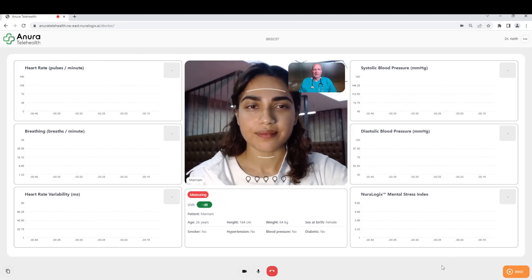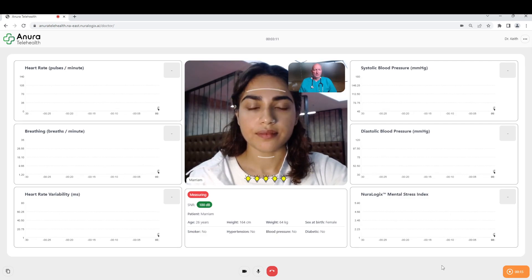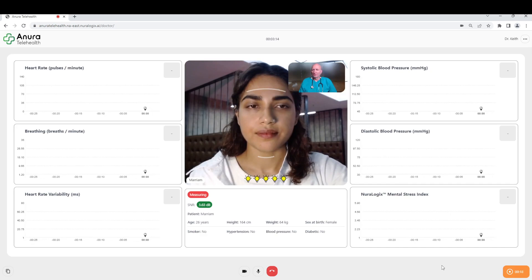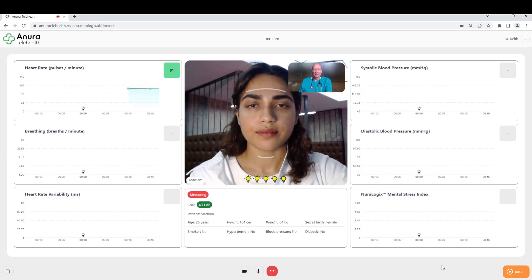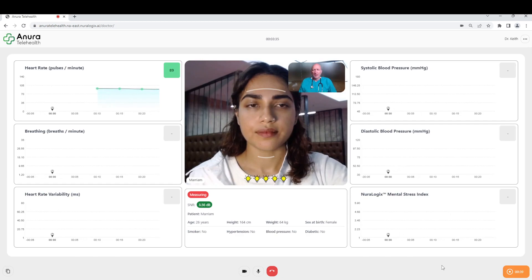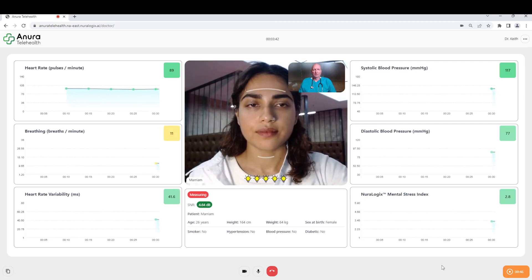If I were visiting you by telemedicine conference, Miriam, I would be discussing your physical state and I would have you just hold still for a few minutes while we capture some readings. We can see that Miriam is very relaxed — hopefully. The beauty of this technology is it also gives us prompts that we're getting good signals. We're able to see the pulse wave, and when we're getting a good signal we have indicators of lighting: there are five stars across the bottom, which means the lighting is even and we're able to see all those regions of interest. The signal-to-noise ratio is also an indicator of how strong the signal is that we're capturing for the pulse wave.